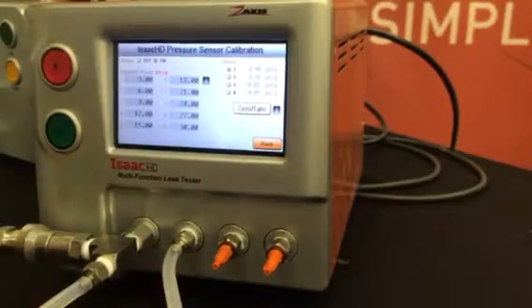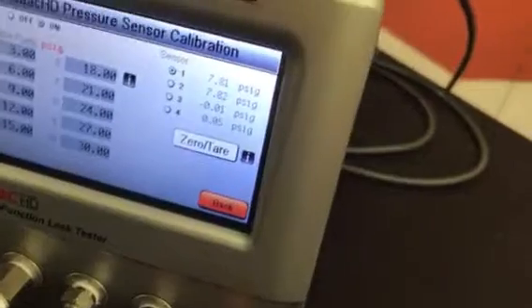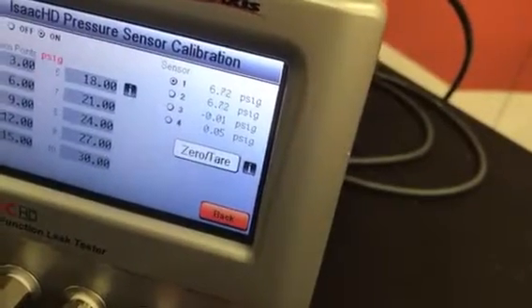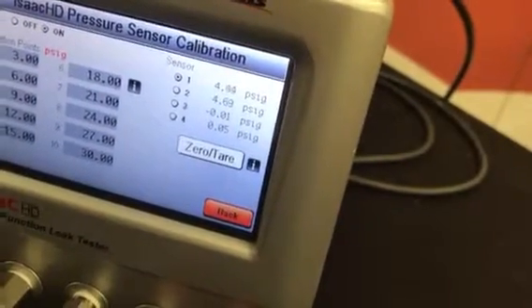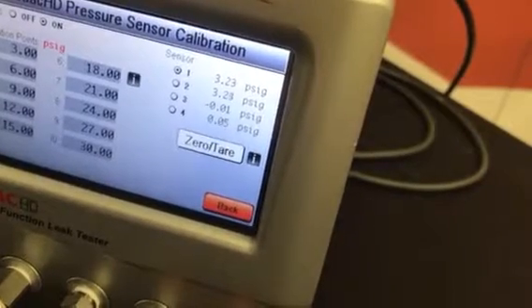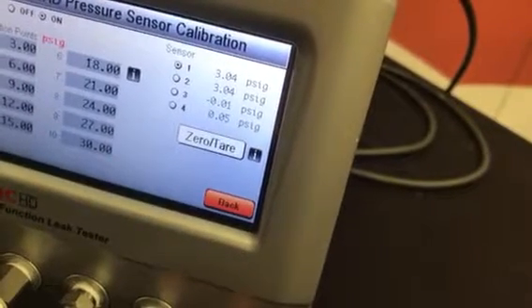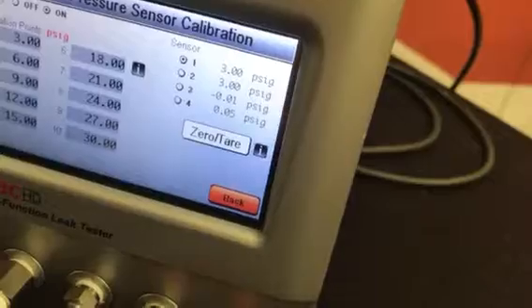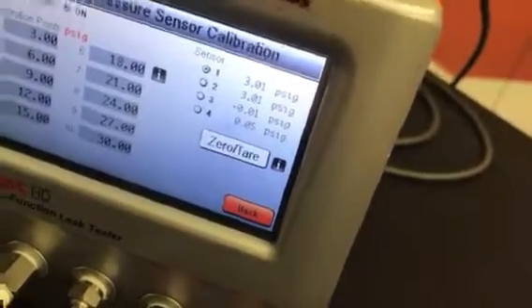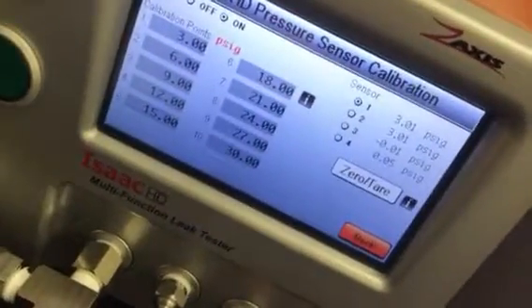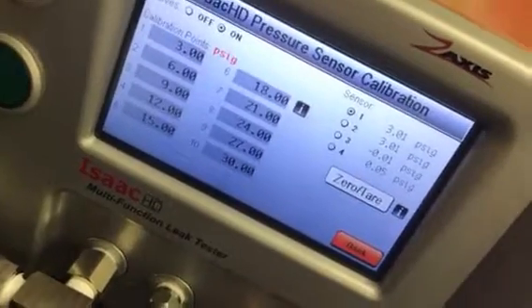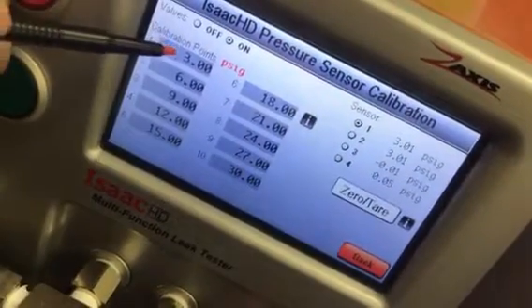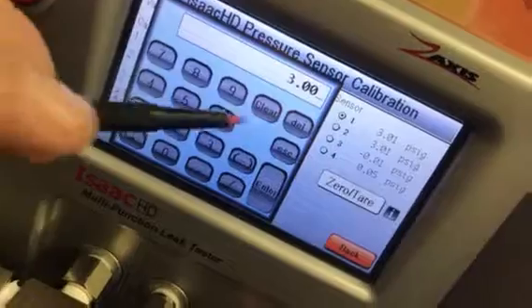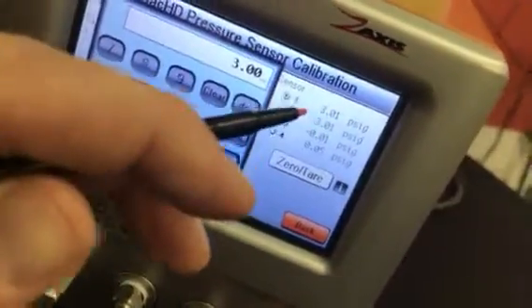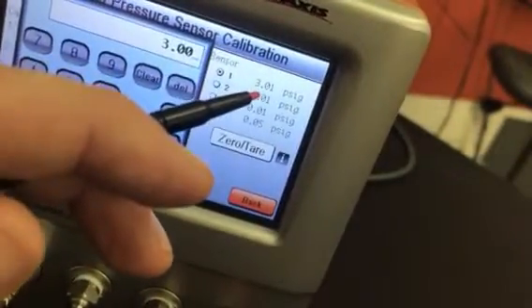I'm going to back that down. Make sure you can read this. I'll zoom in a little. I'm going to back that down so it says 3 PSI. So there's 3 PSI. My sensor's reading that. So my number 1 cal point is 3. So what I do is I touch number 3. 3 pops up on the screen. I'm calibrating my number 1 sensor.